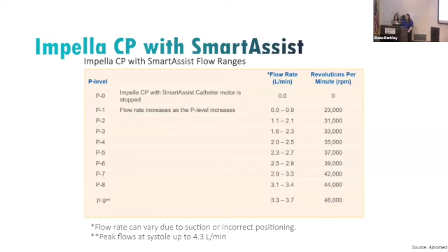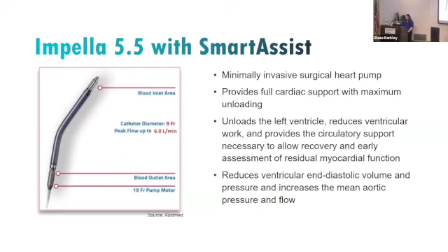Right, here we have the Impella 5.5 with Smart Assist. It's a minimally invasive surgical heart pump that provides full cardiac support with maximum unloading, allowing the heart to rest and recover. It unloads the left ventricle, reduces ventricular work, and provides the circulatory support necessary to allow recovery and early assessment of residual myocardial function. Similar to the CP, the Impella 5.5 has an inlet, outlet, and optical sensor. The difference between the two is the 5.5 doesn't have that pigtail at the end of the catheter keeping it in place. It moves blood in the same way as well. So it pulls the blood from the ventricle through the aortic valve and into the root of the ascending aorta. And since the blood is moving in the same direction as a CP, the flow still reduces ventricular end-diastolic volume and pressure and increases the mean aortic pressure and flow.